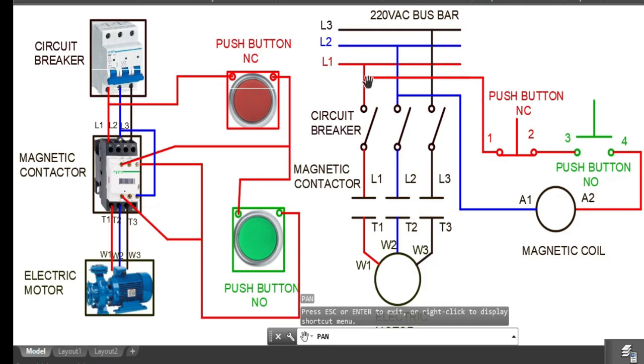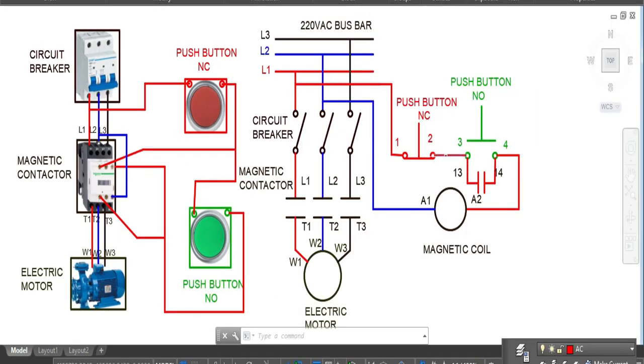So here we have to trace the control wiring. From line 1 it goes to the push button. Also here it goes to the push button, and then the out goes to the normally open push button, then going to the A1. Actually, this is the A1, this is the A2. And then the A2 is going to line 2. Okay, this is the complete circuit of the block diagram and schematic diagram for the stop-start motor controller.